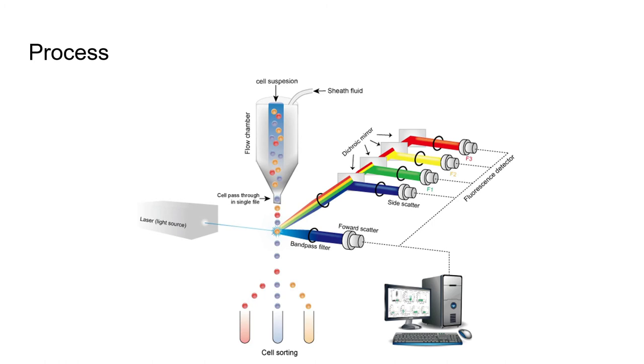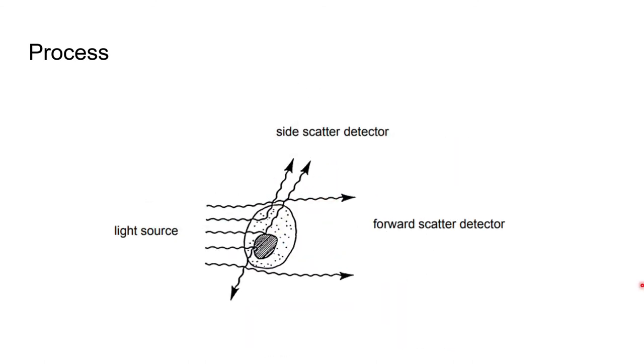The way this works is cells pass through a tube one cell at a time. As the cells pass in front of the laser light, the light source is eclipsed, and the amount of light blocked is read by the forward detector as the cell size. Also, as light passes through the cell, it becomes scattered away from the midline — the more contents within a cell cytoplasm, the more scatter that results. This is read by the side detectors as complexity of the cell.